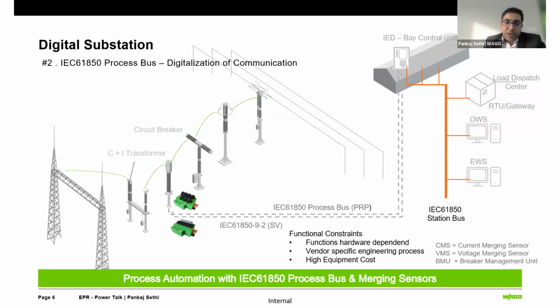With the process bus technology, we have voltage merging sensors and current merging sensors. They acquire data directly from the instrumentation transformers in the yard, convert that information into sampled values based on the process bus standard, and send the data over the network using PRP to the IEDs. The IED also communicates through these messages to the breaker management unit for breaker management.